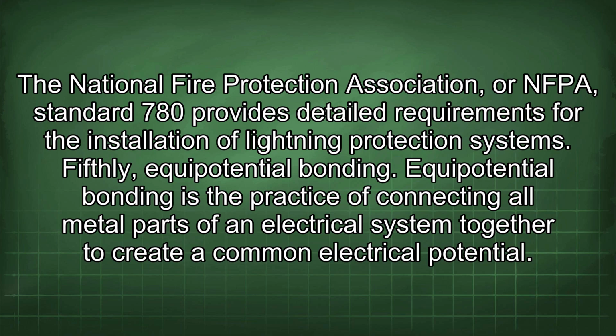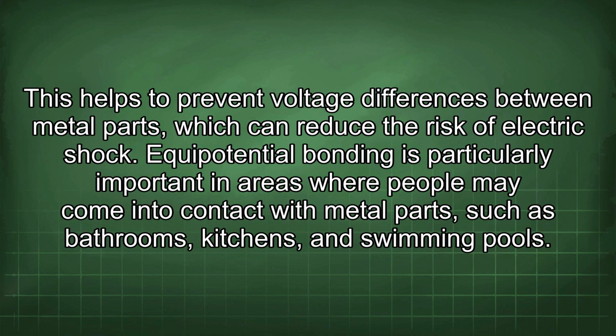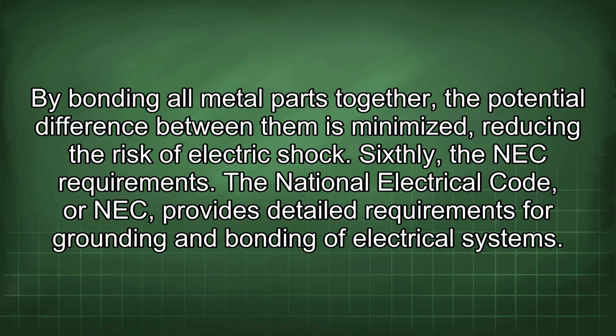Fifthly, equipotential bonding. Equipotential bonding is the practice of connecting all metal parts of an electrical system together to create a common electrical potential. This helps to prevent voltage differences between metal parts, which can reduce the risk of electric shock. Equipotential bonding is particularly important in areas where people may come into contact with metal parts, such as bathrooms, kitchens, and swimming pools. By bonding all metal parts together, the potential difference between them is minimized, reducing the risk of electric shock.